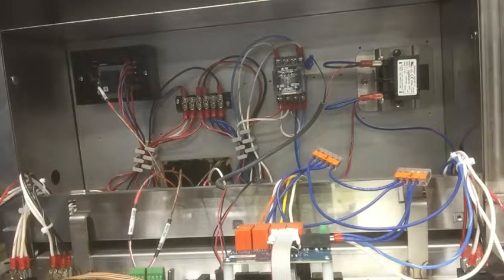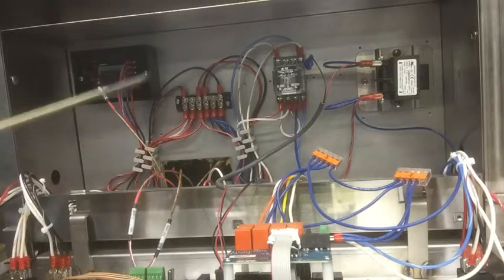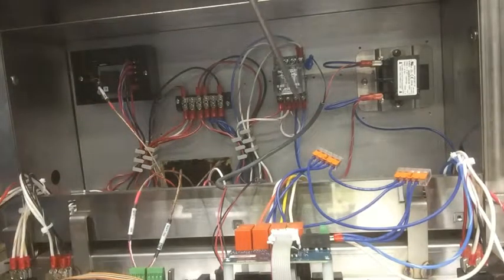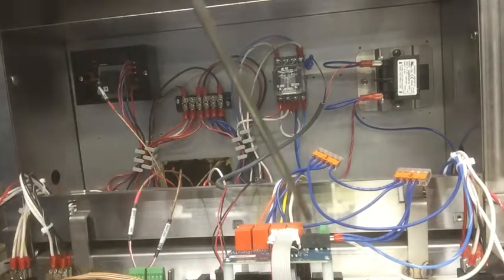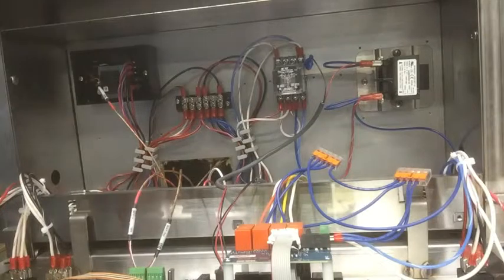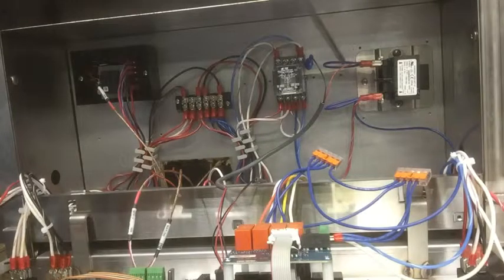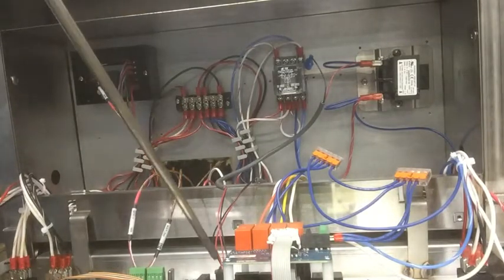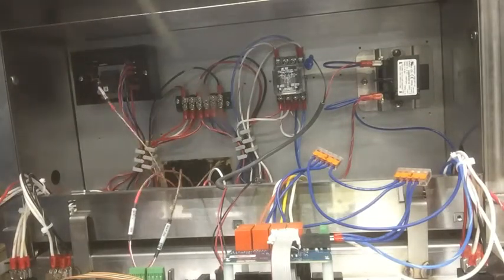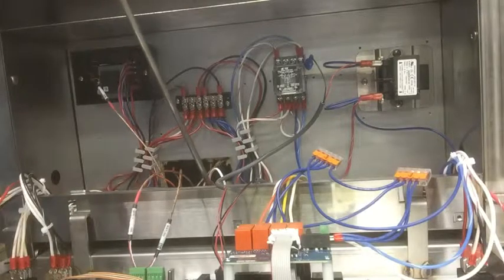Here we have the inside of the control panel. In the back plane, we have our high limit module, a 450-degree trip with a high limit probe wired in right here. Over here we have our heat relay. The heat relay is powered by the controller. Whenever the temperature drops 3 degrees below set point, which is our hysteresis, it will activate this relay, which will in turn pull in the heat contactor in the back and our yellow heat light. We have our control transformer, which provides 20 to 26 volts AC. It is protected by this 1 amp fuse, and this is solely for powering up the controller. That's all it does, just power up the controller. And then right here we have our alarm module. This alarm, for any kind of issues or an end of cook cycle, is the only alarm on this fryer.